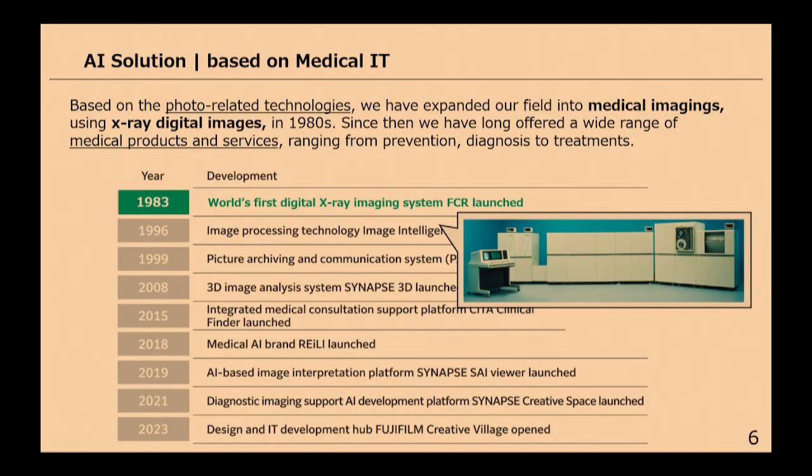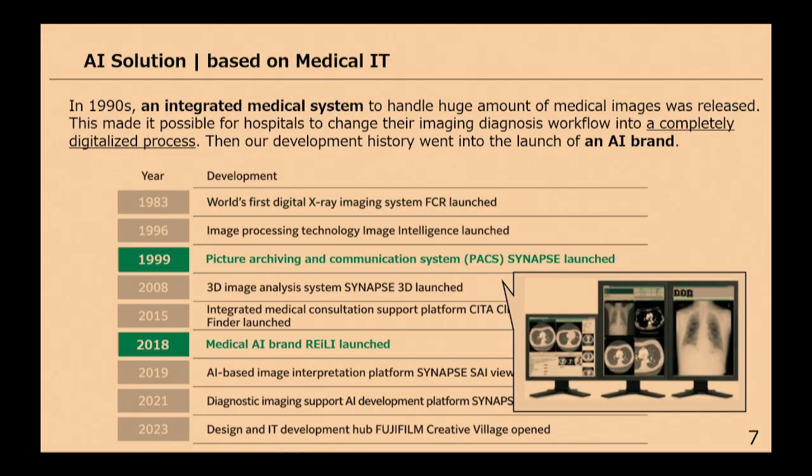This is actually an example of the first computed radiography system used in the medical industry, which you can see we've come a long ways. That was a very large system, but that was the very first one of its kind. That was the first CR system used in medical. So again, the main purpose was to reduce the amount of dose to the patient, to make it faster. Less radiation on your body is good. And then we just progressed from there. So that was back in the 80s.